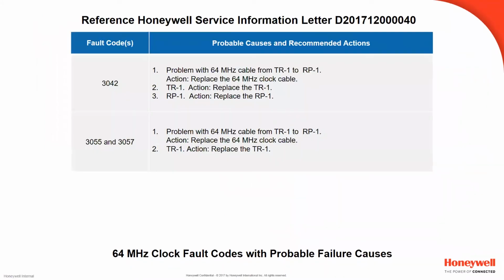Yeah, and the 3042 is the RP pulse data message communication fault. And when this fault occurs, we recommend to first check the continuity and condition of the 64 megahertz clock cable to check if the wiring is satisfactory, and only then replace the TR as the second troubleshooting step. If the fault continues, then the RP could also be faulty in logging this fault.